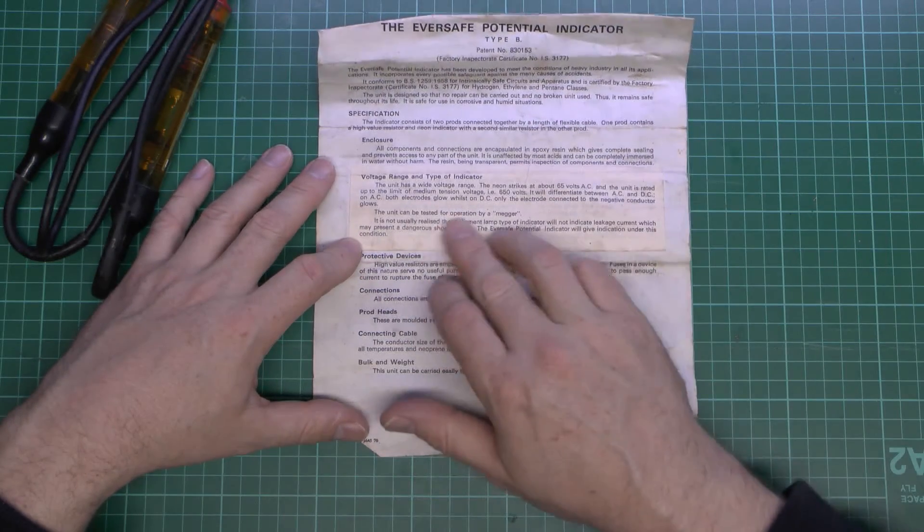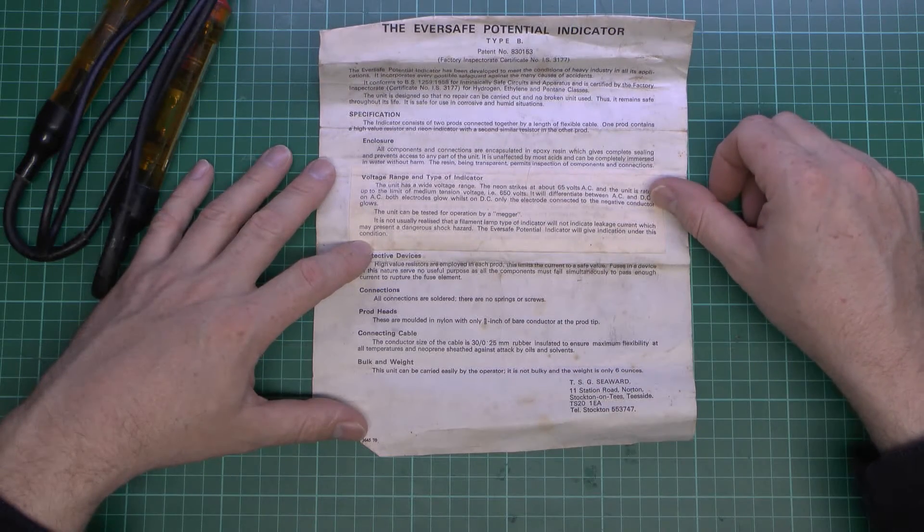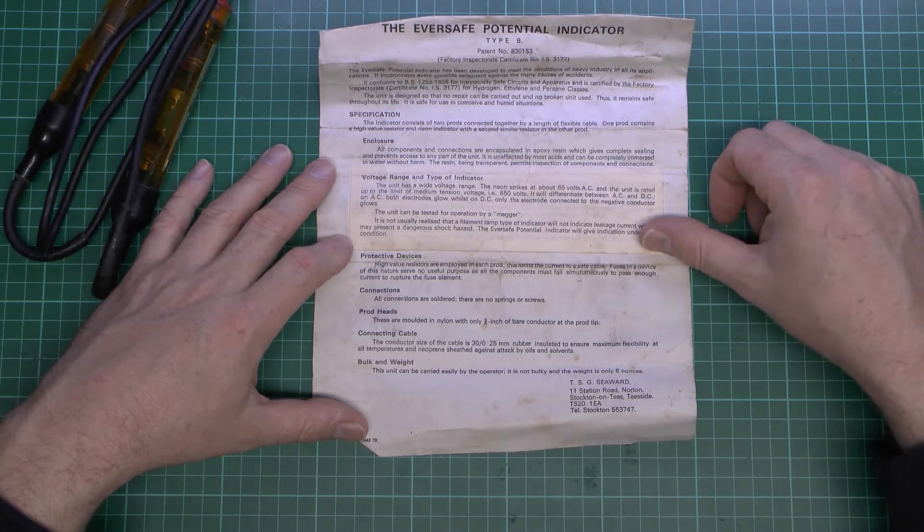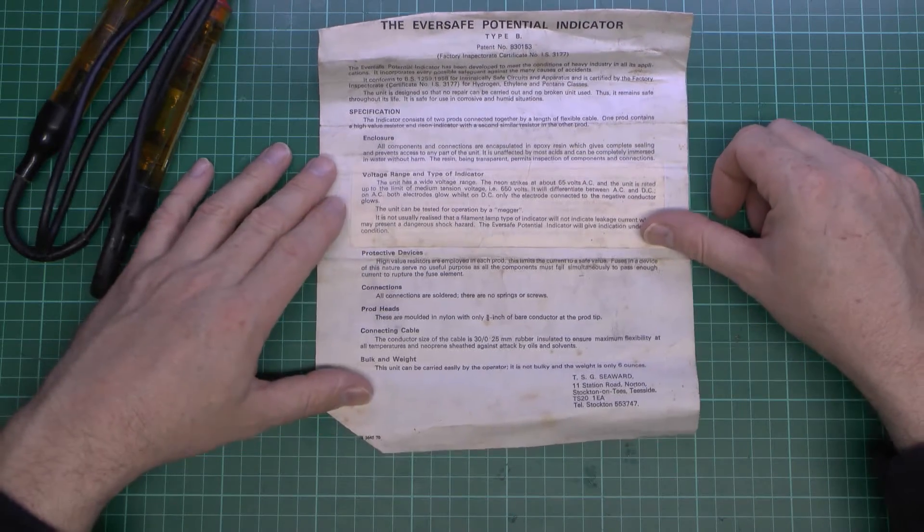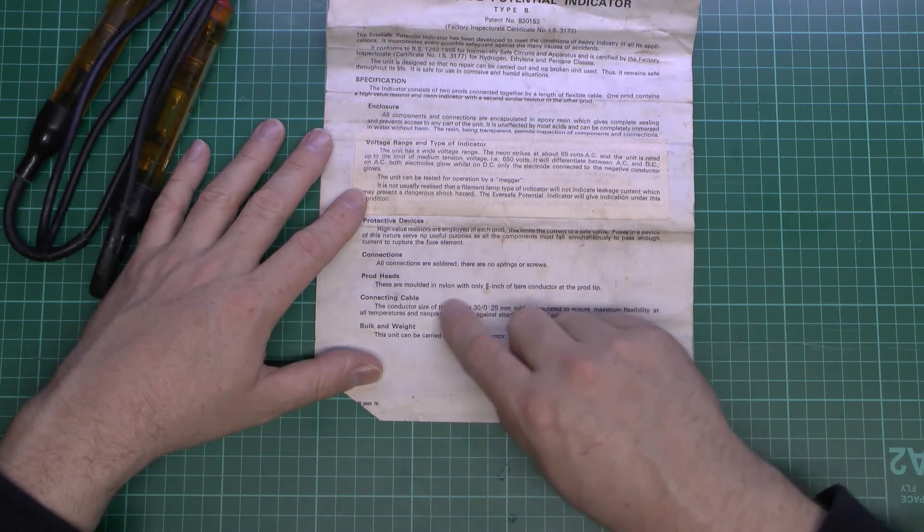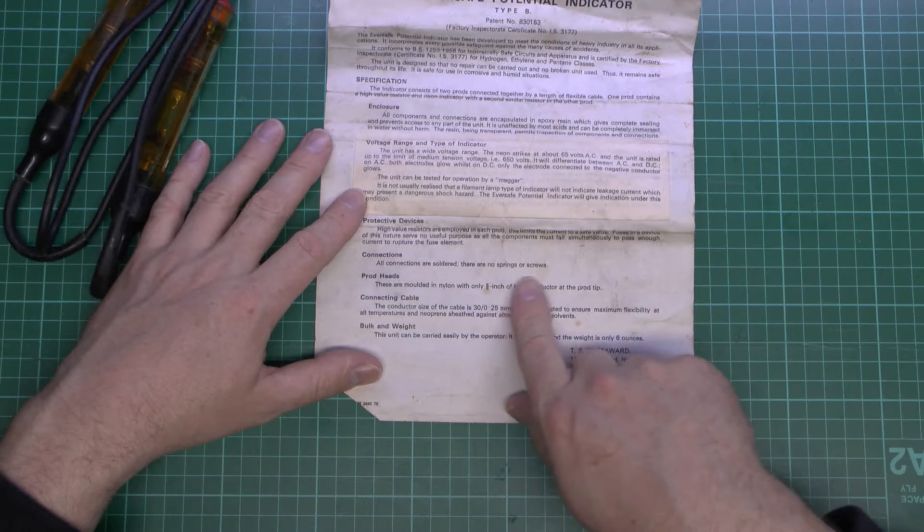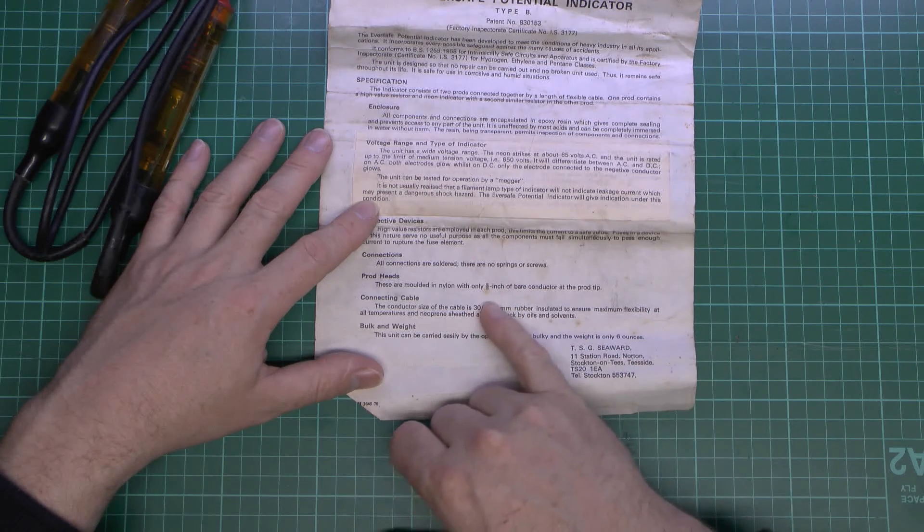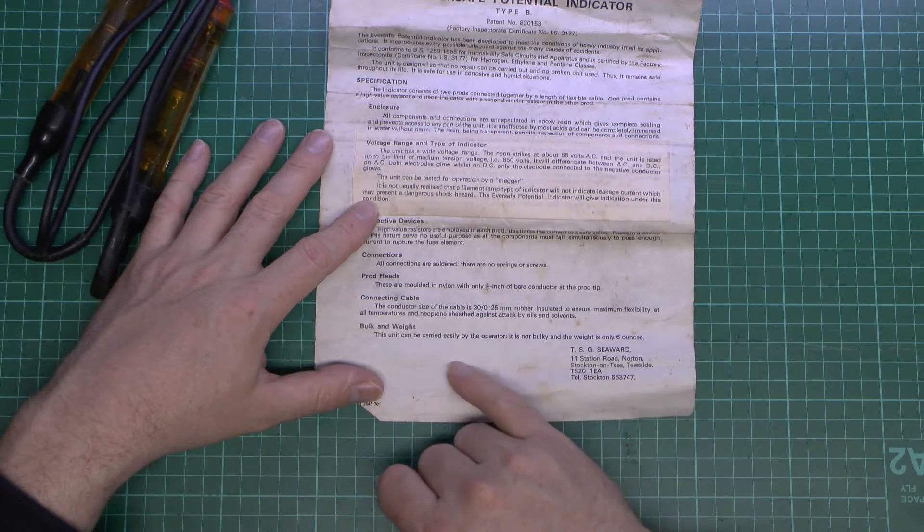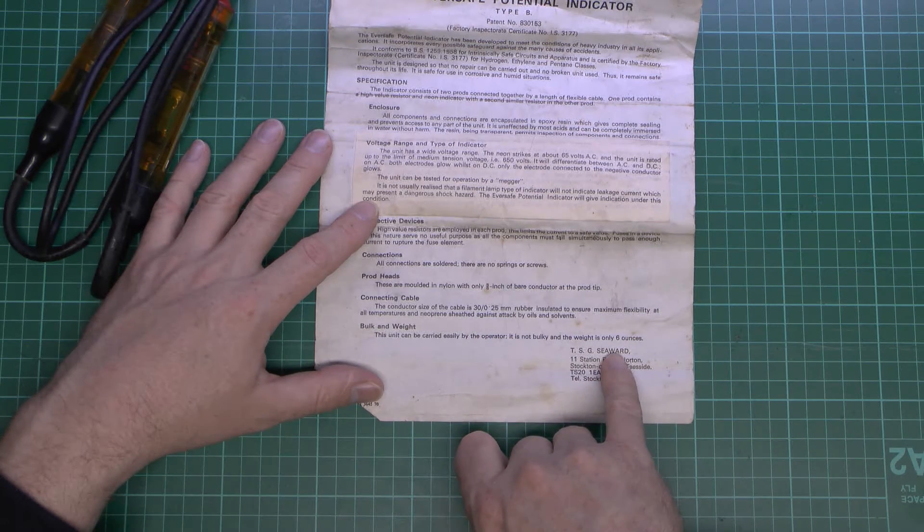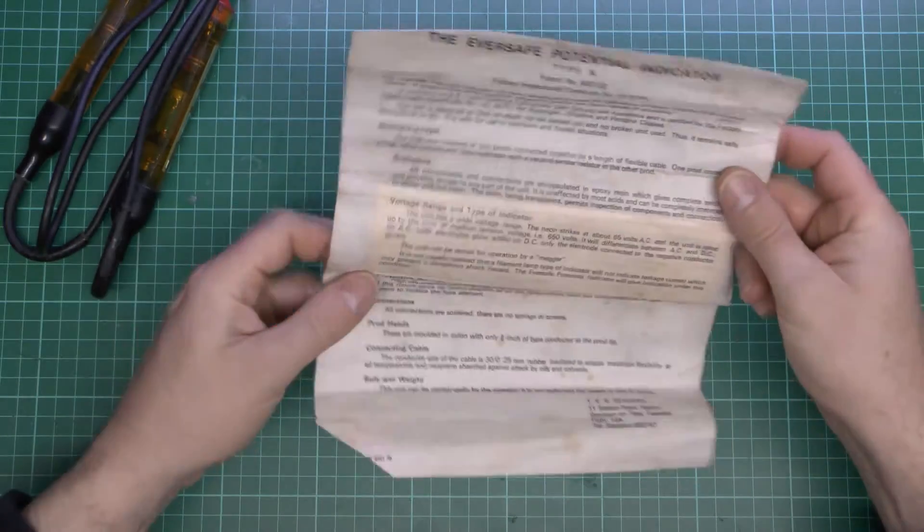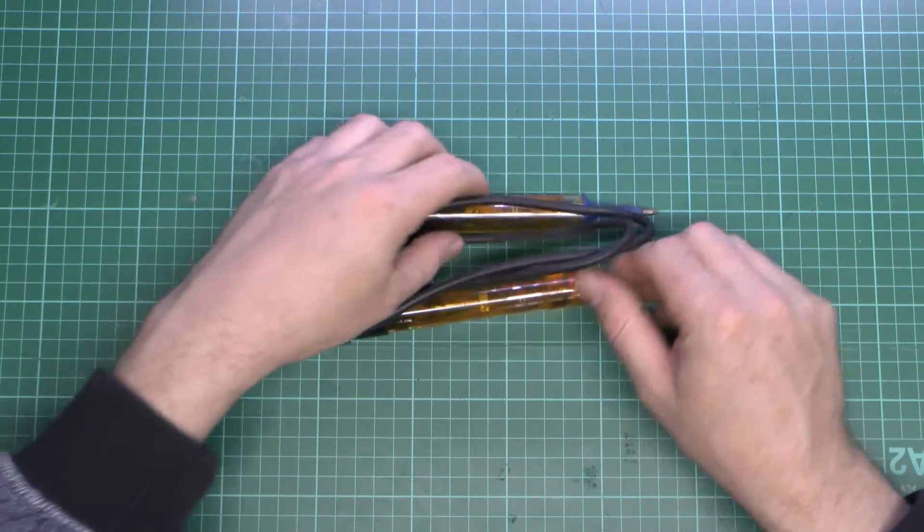You can test it for operation by megger, which is one of those things that puts out 500 volts to check the quality of insulation, and that's well within the range it's designed to detect. It has resistors in each prod. All the connections are soldered, no springs or screws, and the ends have only 5/8 of an inch of bare conductor, rubber cable, and it only weighs 6 ounces. Let's have a look at the item itself.